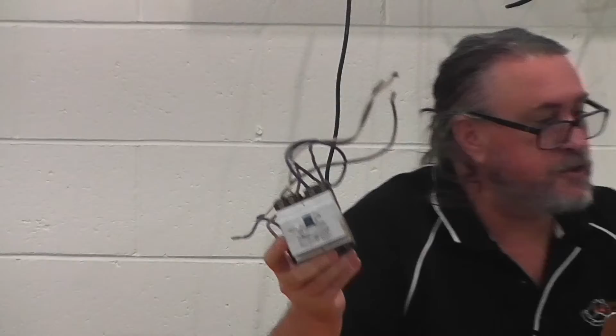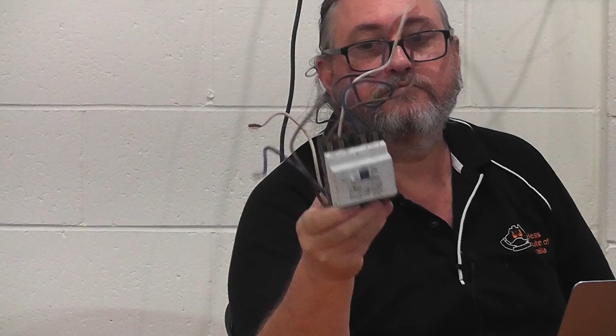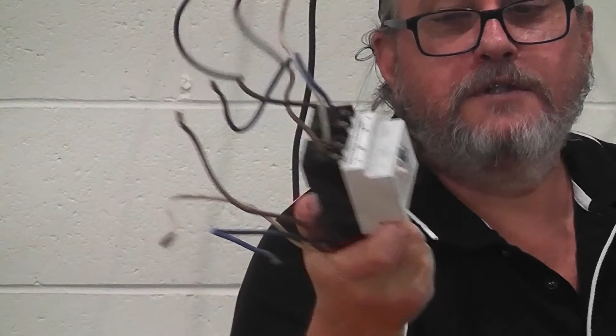And the one that's probably most important, well, it's not the cure-all, but it is important, is the RCD, residual current device, or your earth leakage circuit breaker. That's a 4-pole variety. Very popular at the moment because it's cheaper to put those in than to put the individual RCDs in. This one is a single pole RCD, built in with a circuit breaker as well, whereas that is purely RCD and it can protect up to 3 circuits. That's useful if your board doesn't have a lot of room. But if something does trip and you're not in your house, your fridge is going to go off and you're going to come home to a stinky house. So I always thought these things are a good idea because if something trips off one circuit, your fridge has got a good chance of keeping going.